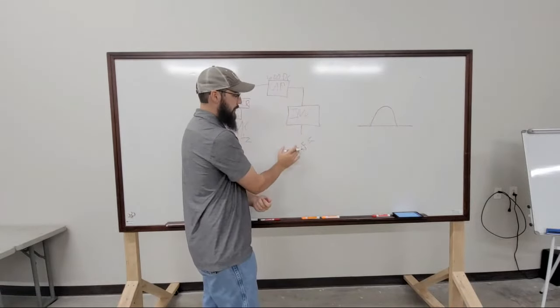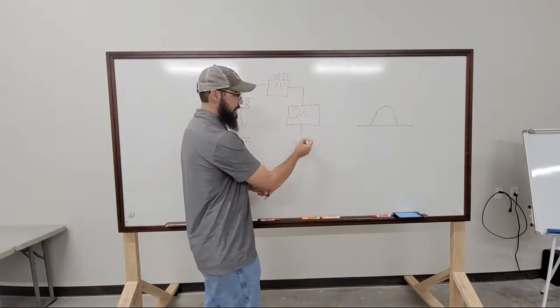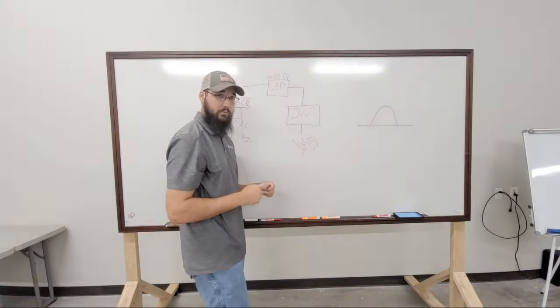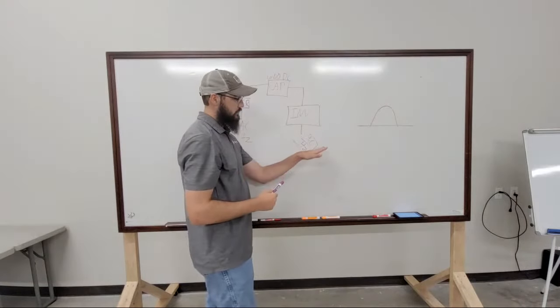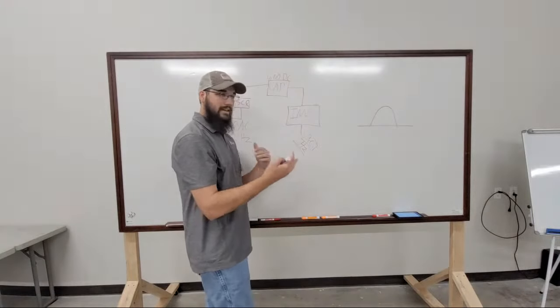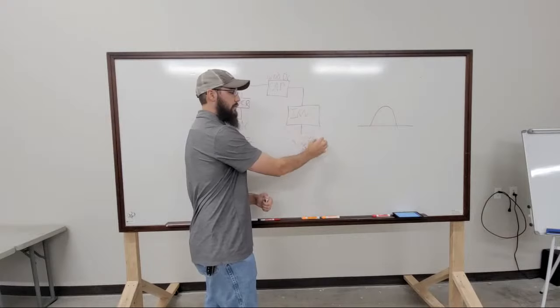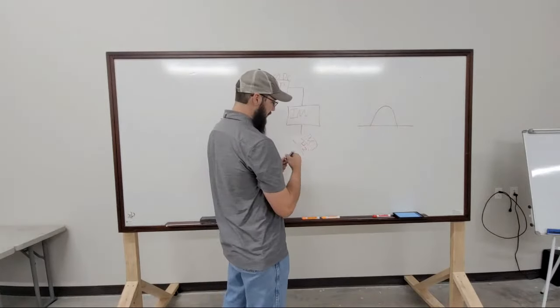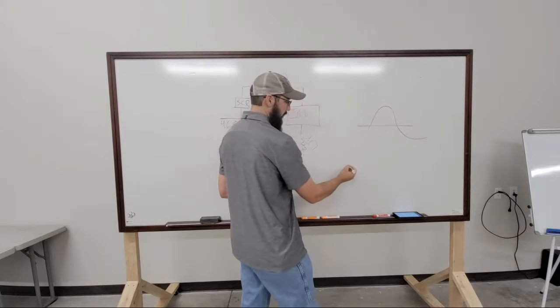The main thing we're trying to control at this point is the Hertz value. If you put your meter on the output of the drive, you would see the voltage look kind of weird at times. You have to have a true RMS meter to get an accurate reading. At a lower Hertz range, you might actually see the AC voltage look lower, and in theory it really is lower — but let's focus on just the Hertz side of that control function. Coming into the drive we have an AC sine wave; coming out of the drive it's going to be what's known as pulse width modulation.